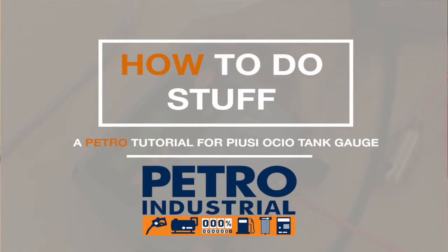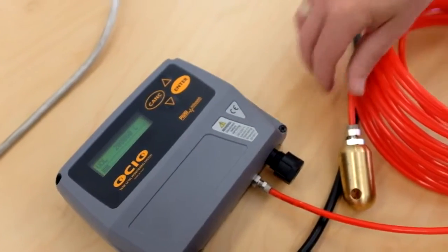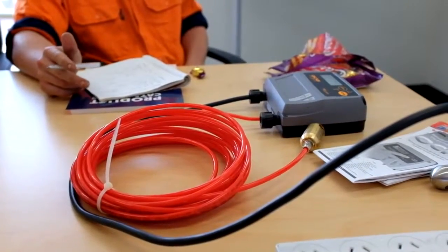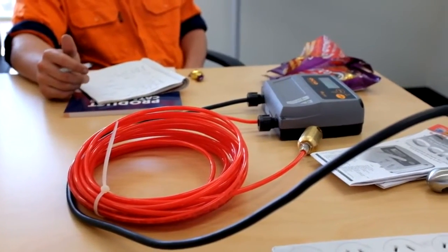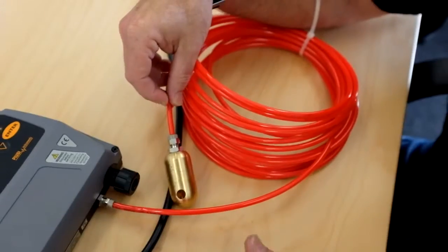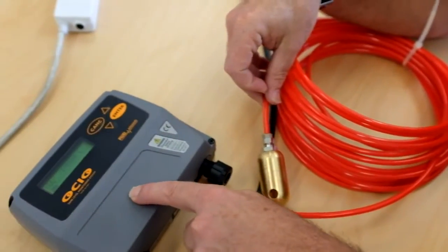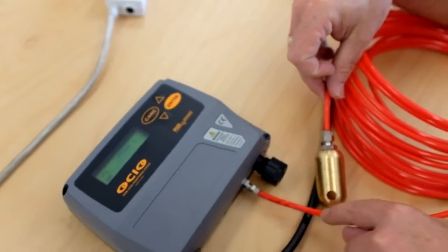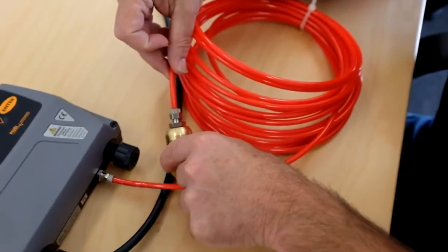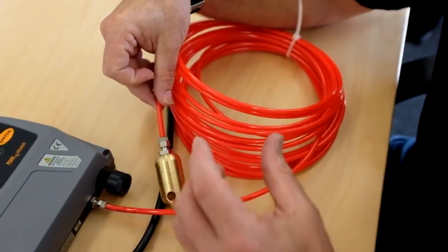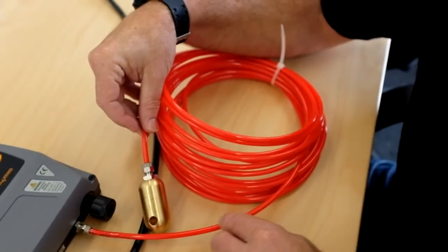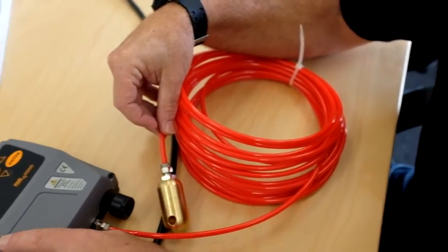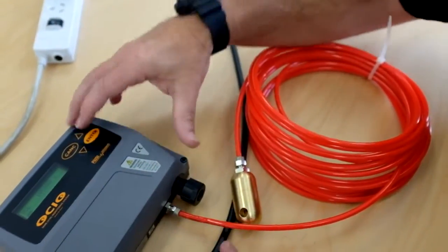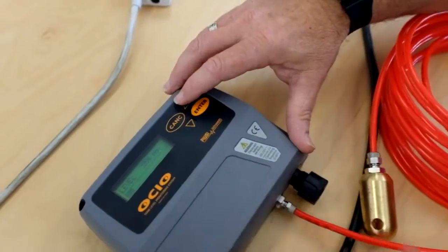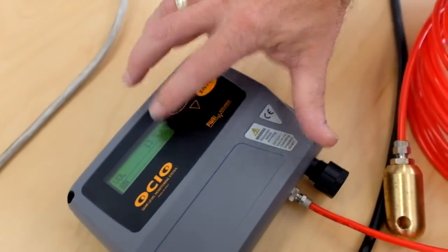So we've got an OCIO tank gauge unit, standalone. The maximum distance you can have the probe, which goes in the bottom of the tank, to the unit is 12 metres, okay? So how it works, this has an air pump in it, which you can hear running now. It's pumping air down through this red tube, out into the bottom of the tank. It's doing a mathematical calculation of the back pressure of the air into this, and it relates to litres, millimetres in height, or percentage of volume.